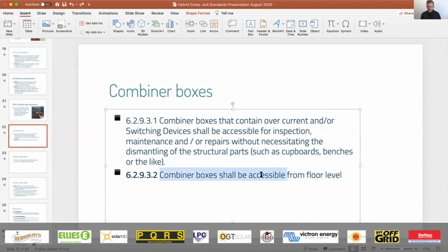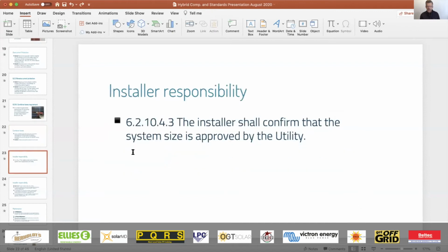It also says combiner boxes shall be accessible from floor level. Guys, I've seen photographs of installers sticking combiner boxes up against the ceiling -- that's illegal. The previous standard says you shouldn't require a step ladder to access it. The combiner box is there to assist with the safety of your installation, so it has to be accessible.